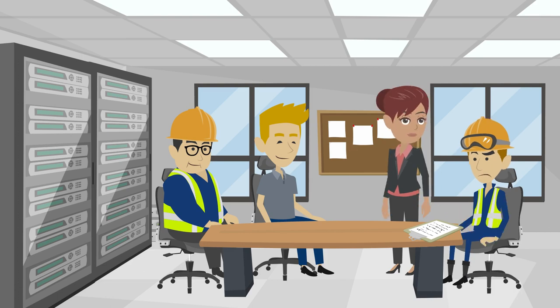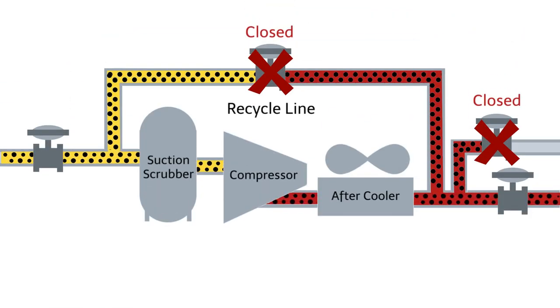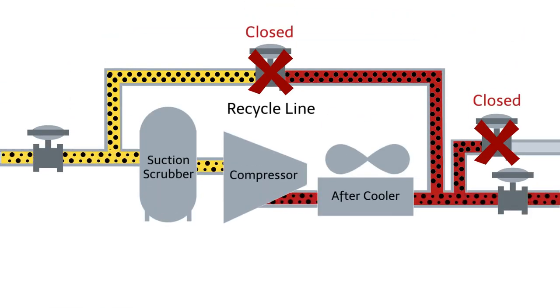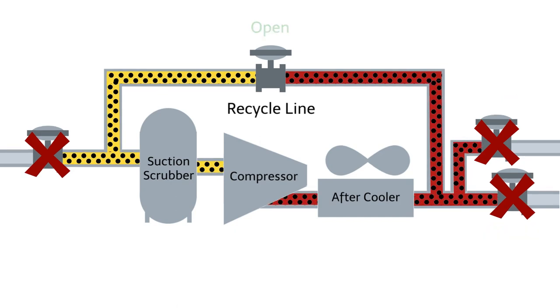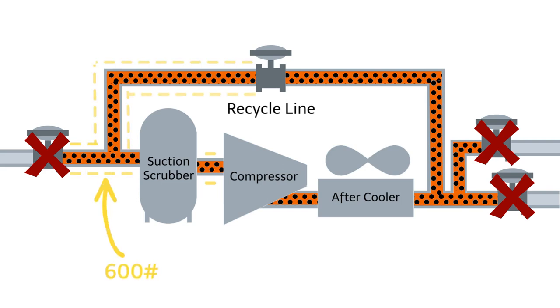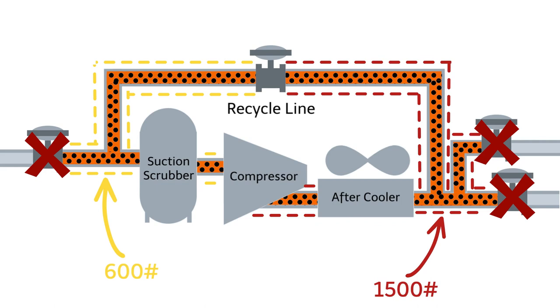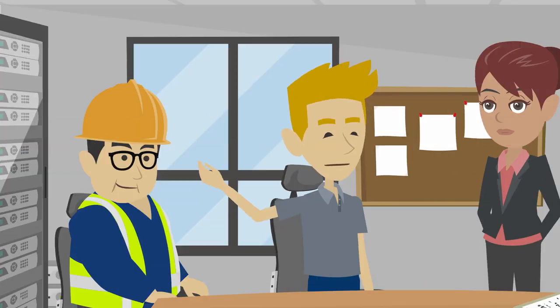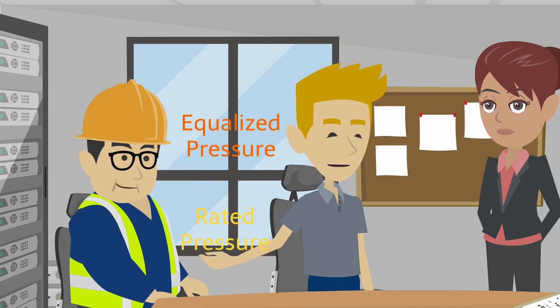How does that occur? There's a flow path that we have not discussed yet — the recycle line around the compressor. When the compressor shut off, the recycle valve opened. This created a path between discharge and inlet and allowed pressure to equalize around the compressor. The inlet has 600-pound piping, while the outlet has 1500-pound piping. The equalized pressure was higher than the rated pressure of the inlet piping.